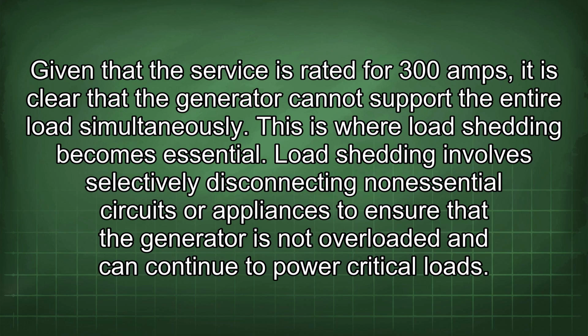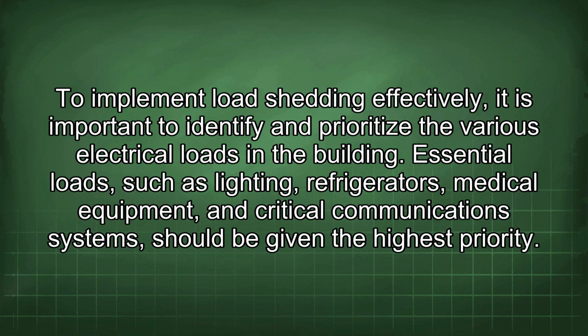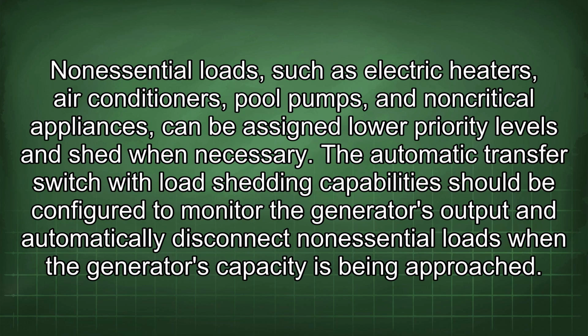Load shedding involves selectively disconnecting non-essential circuits or appliances to ensure that the generator is not overloaded and can continue to power critical loads. To implement load shedding effectively, it is important to identify and prioritize the various electrical loads in the building. Essential loads, such as lighting, refrigerators, medical equipment, and critical communications systems, should be given the highest priority.